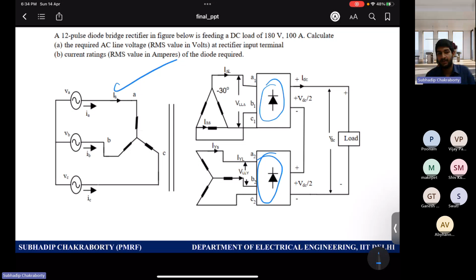Phase shift is very important to cancel the harmonics and improve the current quality at the AC side. That's why transformers are very useful here. Many kinds of transformers exist, zigzag, T, and other configurations, only to give the phase shift and tactfully cancel the harmonics and add them back as per Kirchhoff's current rule and transformation laws. You can see the superposition theorem applied with this transformation, and then the reflection, adding them back to cancel harmonics and improve current quality, because currents are otherwise very much distorted at these sides, as you can understand.